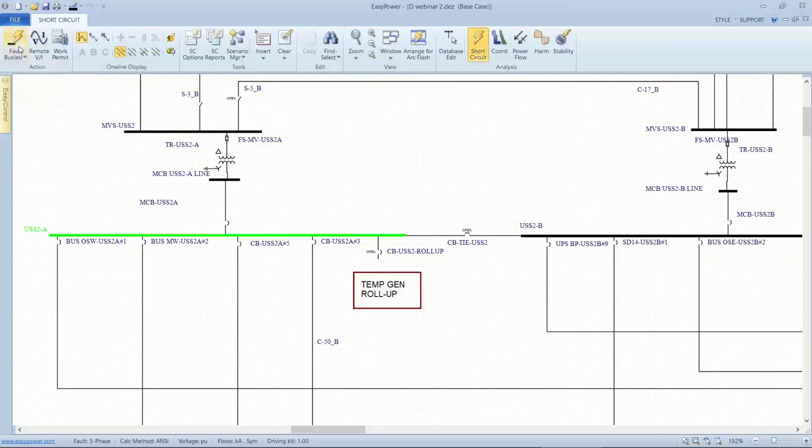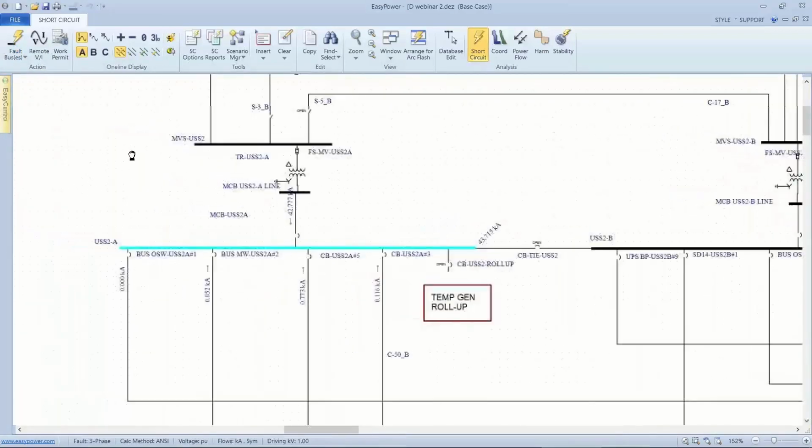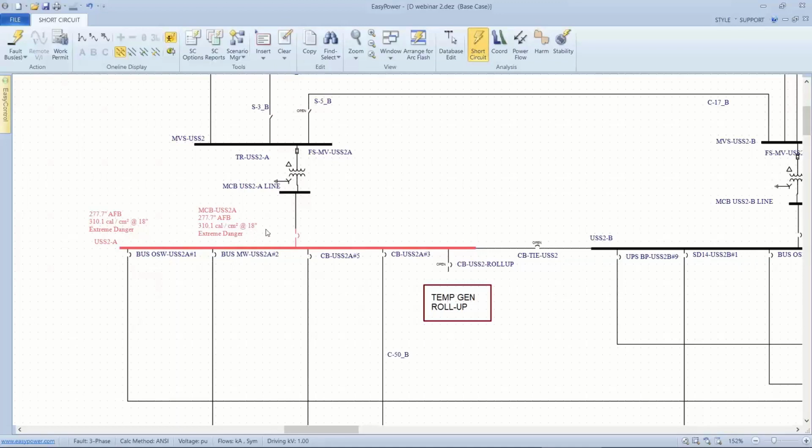we can see that the calculations give us 42,000 amps from above, 52 amps, 770 amps, and 116 amps from below from apparently the loads. And if we look at incident energy, sure enough, we get very high or disconcerting incident energy. So part of the problem is, what are we doing for coordination? So let's go back and look at setup.